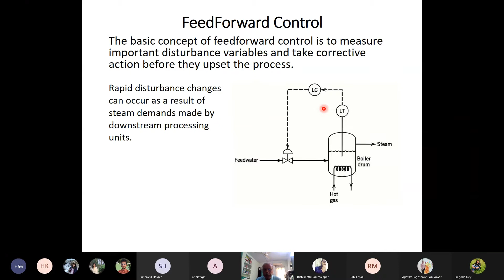What will happen is that rapid disturbance changes can occur as a result of steam demand made by the downstream processing units. And the control system tends to be quite sensitive to rapid changes in the disturbance variable, steam flow rate, as a result of the small liquid capacity of the boiler drum.